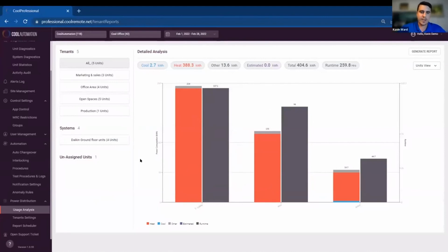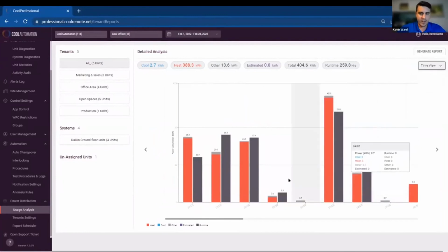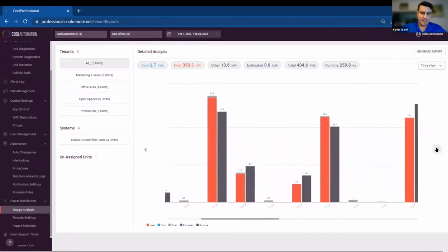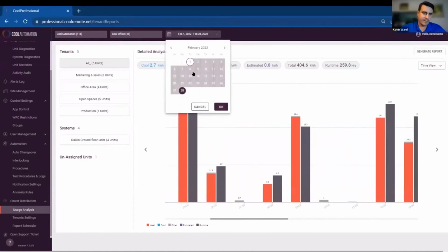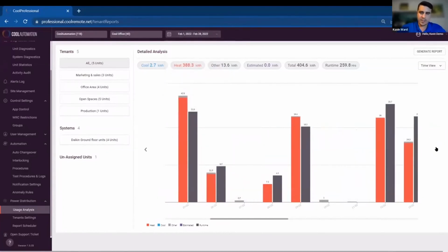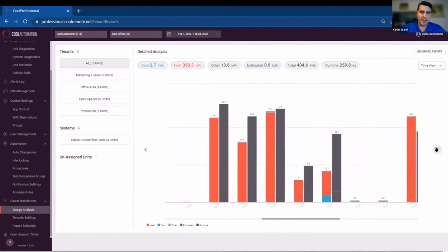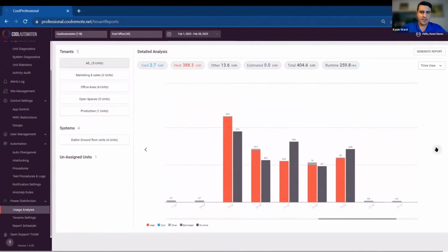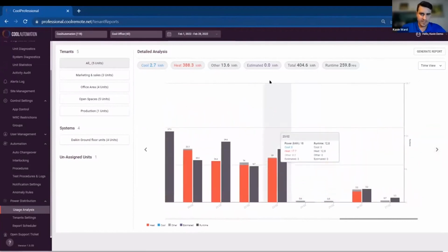So in a multi-tenant application, you can see which fan coils are consuming the most. You get a breakdown of the kWh as well as the runtime, and a breakdown of consumption while the unit was in cooling mode or heating mode. You can look at this unit by unit, or view it on a day-to-day basis. So you can easily see, in this case looking at the month of February, which days consumed more energy on average versus not, and you can also see your weekends pretty easily here as well.